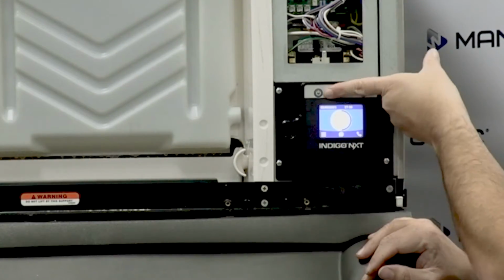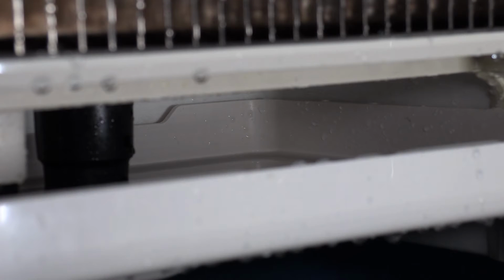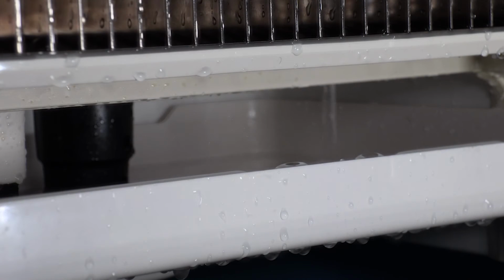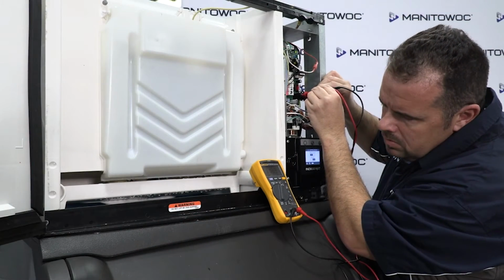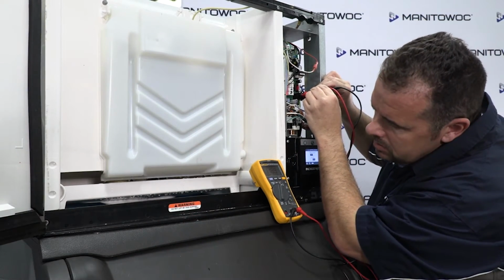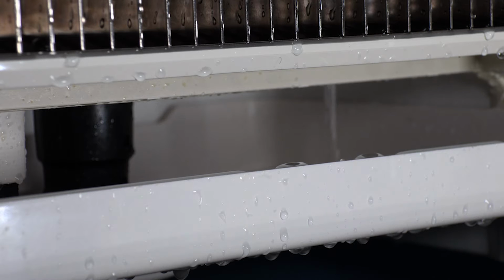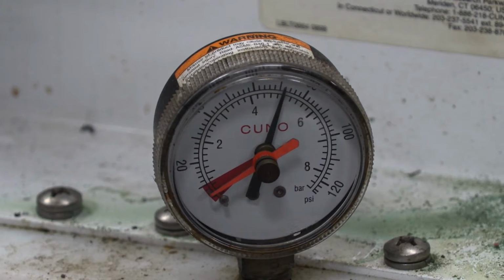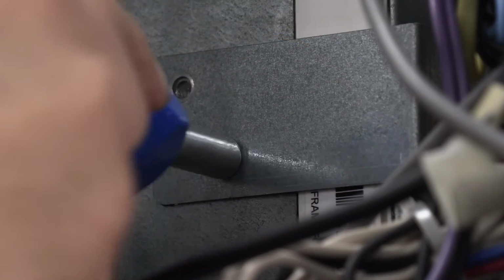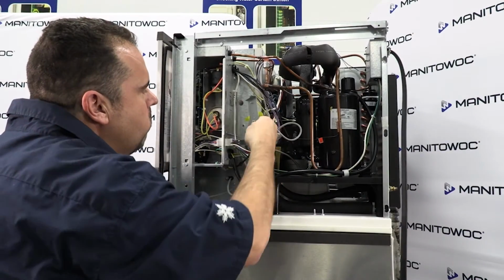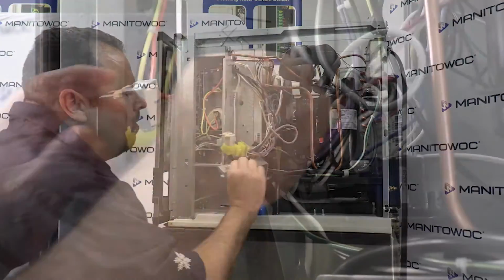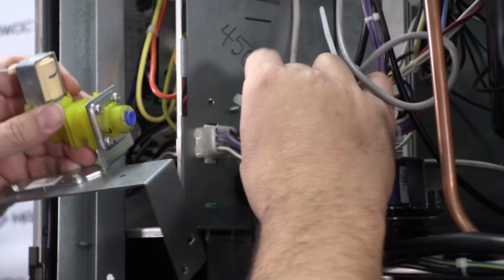Step 1. Turn the machine to off by pressing the power button for 3 seconds and ensuring the water turns off. If water continues to flow in with the ice machine off, check for voltage at the water inlet valve. If voltage is present, replace the control board. If no voltage is present and water continues to flow, verify water pressure is below 80 psig before replacing the water inlet valve. If no voltage is present and water turns off, proceed to Step 2.